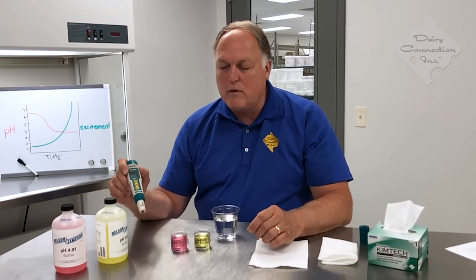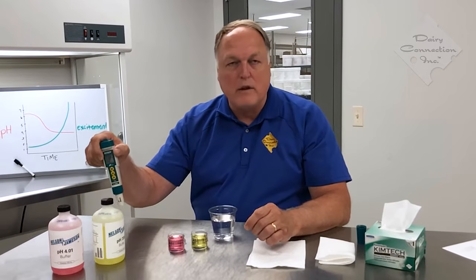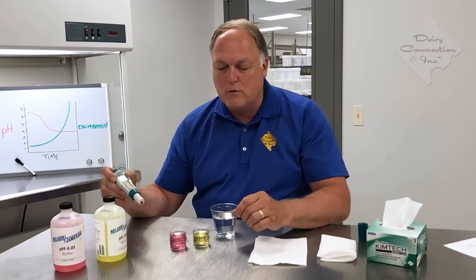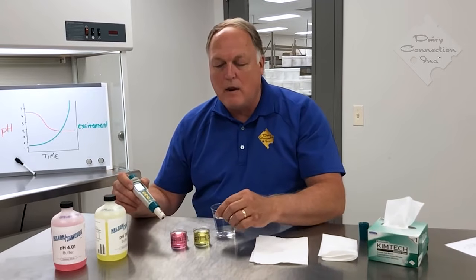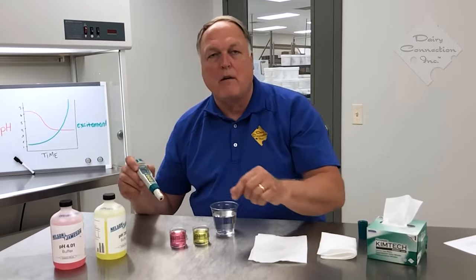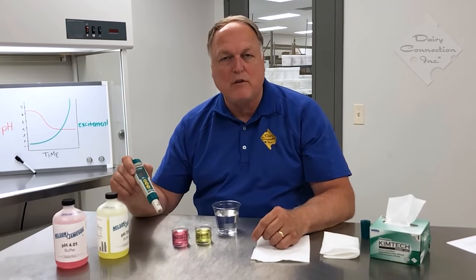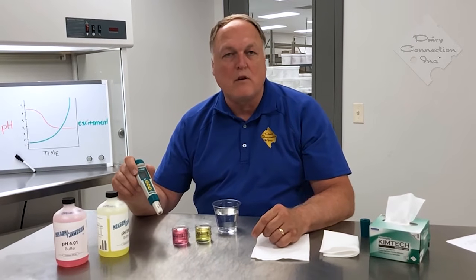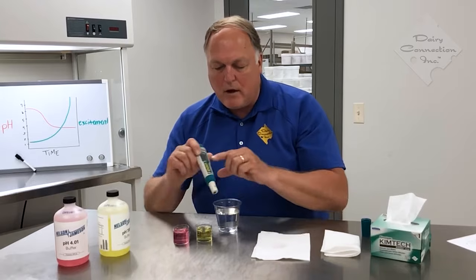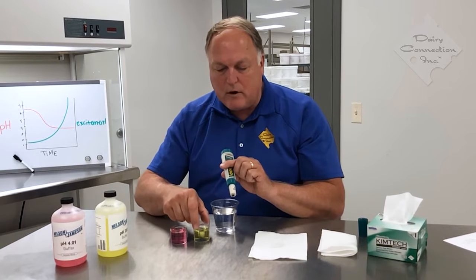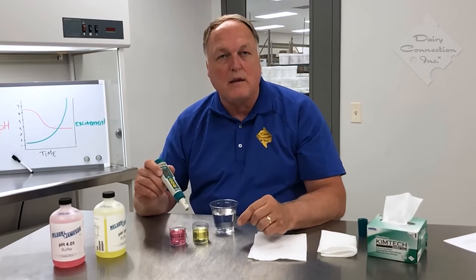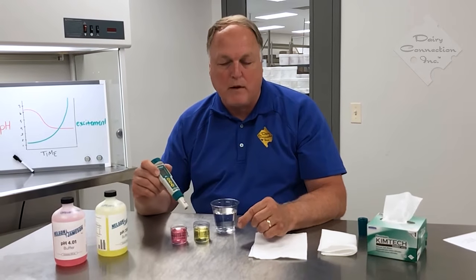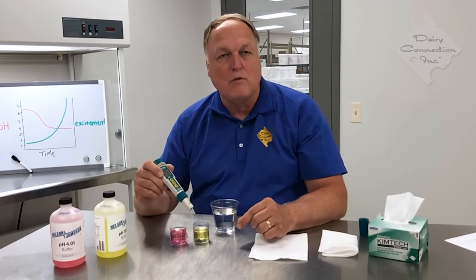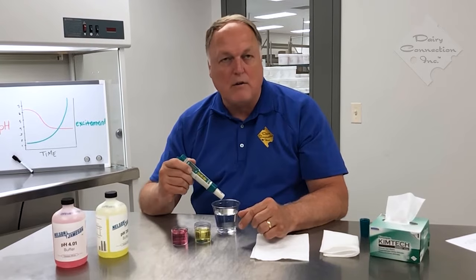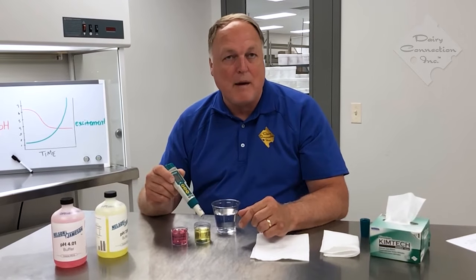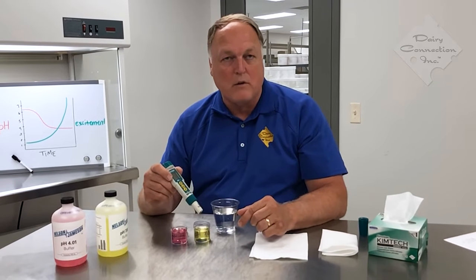It's also important to not dip your electrode into the bottle, but pour some of the solution into another container, and don't pour the solution back into the bottle. That will cause a contamination of the pH buffer, and your calibrations will be incorrect. I would also recommend keeping them covered if you're going to use the same calibration throughout the day to keep evaporation from occurring or from other contamination getting into the product. If you clean your electrode properly, you should not be contaminating with cheese or yogurt or other parts.